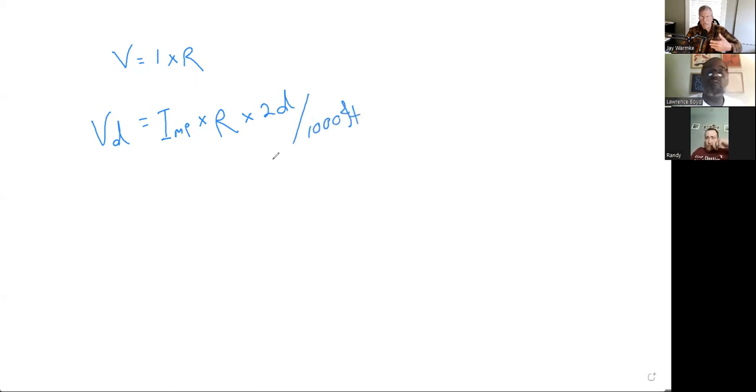Why twice the distance? Because it's a circuit - there and back. When we get the resistance of a wire from the NEC table, it's given in Ohms per 1000 feet, so we need to know how many thousands of feet.